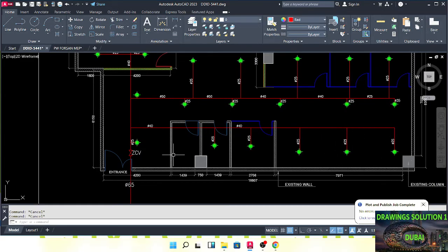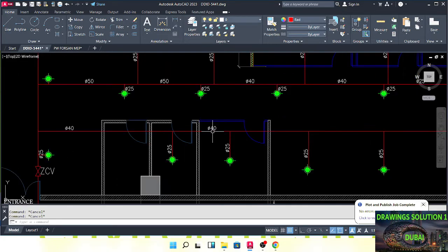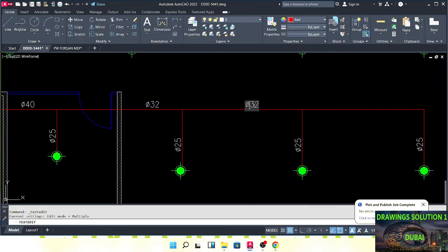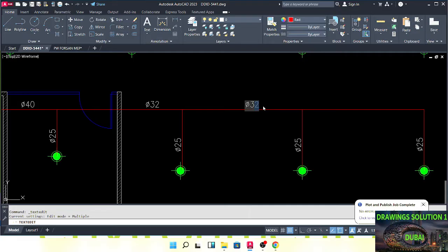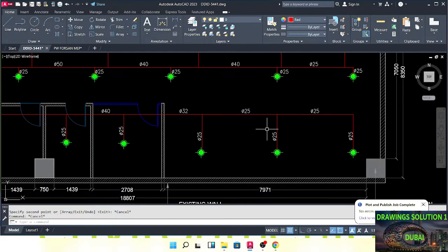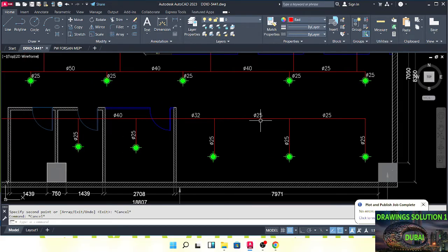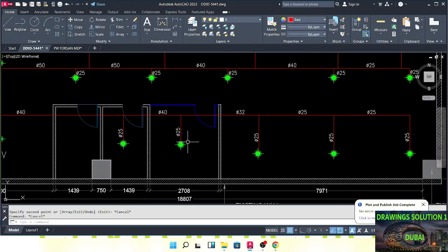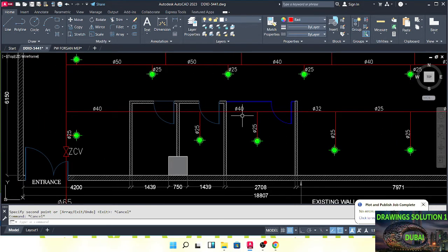We are serving 6 sprinklers with 40mm dia — this is fine. From here there are 3 sprinklers so we change to 32mm dia, and then we have 2 sprinklers, so this will be 25mm dia. To summarize: 2 sprinklers = 25mm, 1 sprinkler = 25mm, 3 sprinklers = 32mm, more than 3 = 40mm, approximately 6 sprinklers = 40mm.